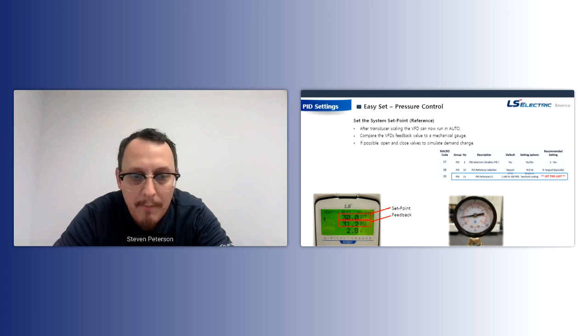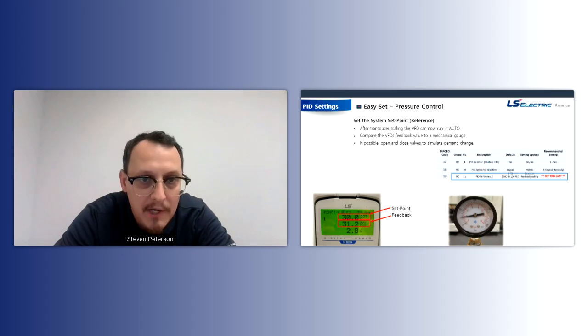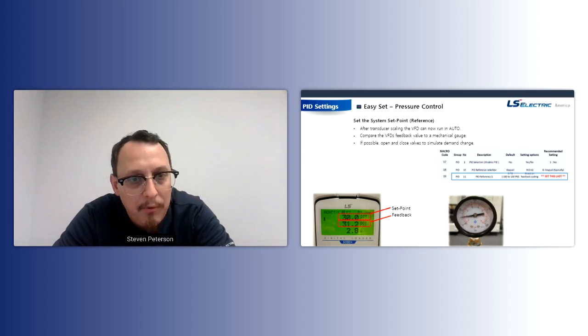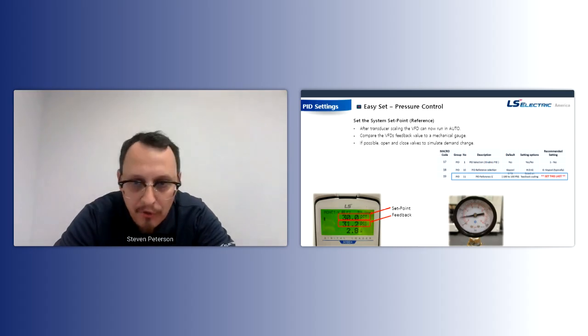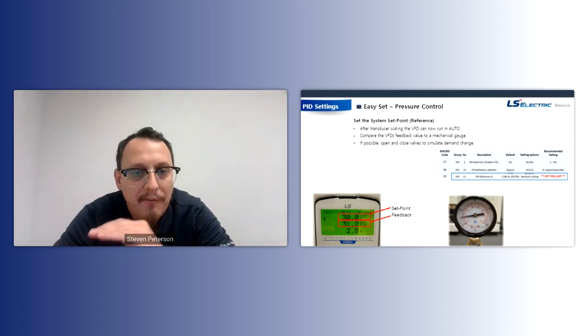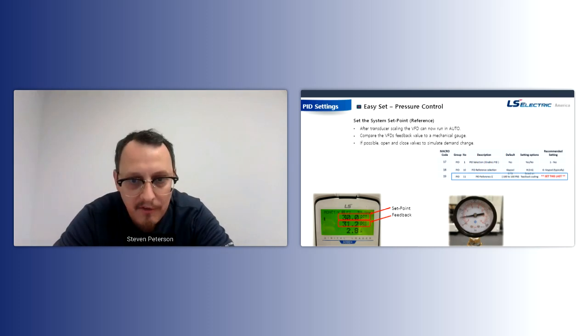Okay. So you can see we have our set point on top. This is an actual picture of a demo I have here where you see the feedback, and the feedback is pretty close to the set point, so the drive's throttling down a little bit. After you have that programmed, you could run your drive in auto, which we talked about before. Close your run command, and the drive's going to compare your set point to the feedback. If the feedback is below the set point, it's going to speed up to build up pressure essentially.